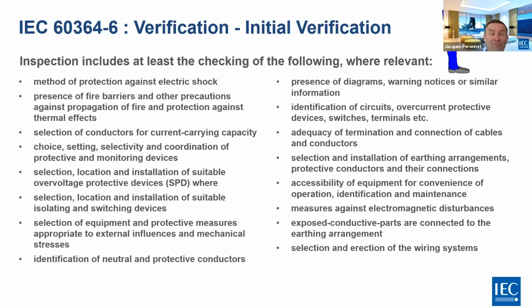You have to verify the presence of the fire barrier or other precautions against the propagation of fire, and the protection against thermal effect. You have to check the correct selection of conductors for current carrying capacity. You have to verify the choice, the setting, the selectivity, and the coordination of the protecting and monitoring devices. The selection, location, and installation of suitable overvoltage protective devices, SPDs, where relevant. You also have to check the selection, location, and installation of suitable isolating and switching devices. The selection of equipment and protective measures appropriate to external influences and mechanical stresses.